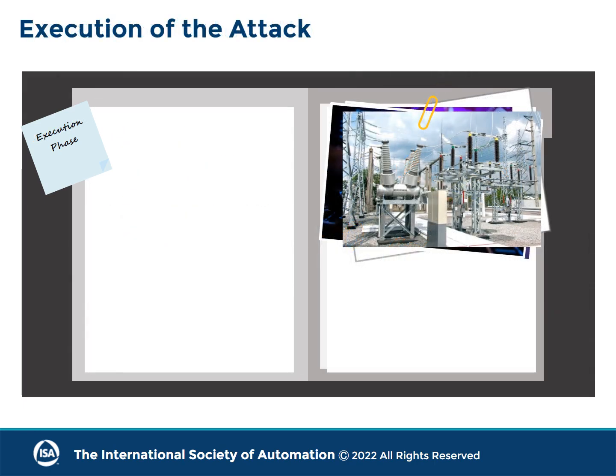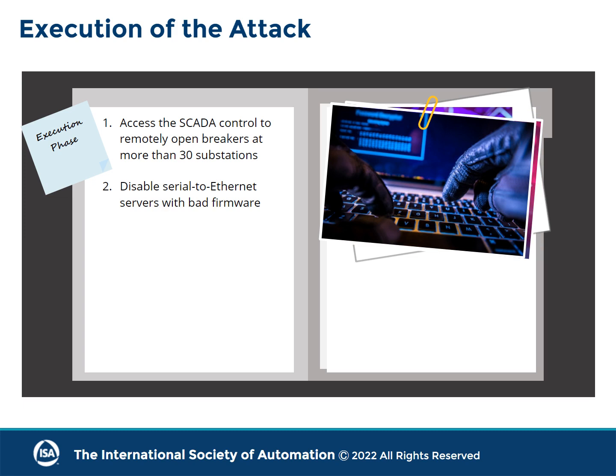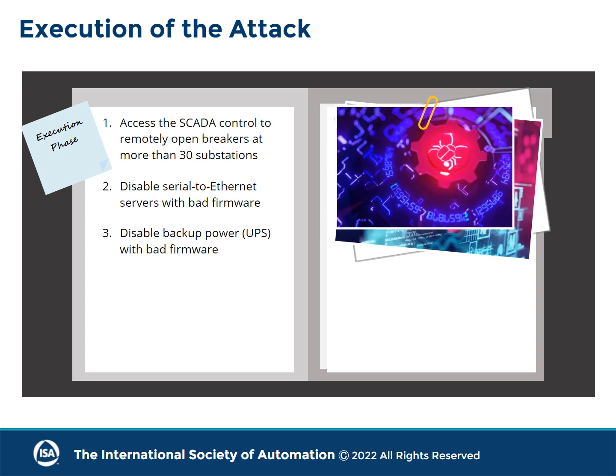The execution phase of the attack consisted of access to SCADA control used to remotely open breakers at over 30 substations. In particular, the serial-to-Ethernet servers used to communicate between SCADA control and the substations were compromised or disabled with bad firmware planted on them, which resulted in total operator loss of view and control of the grid distribution system. The backup power, or UPS, was also disabled with bad firmware.